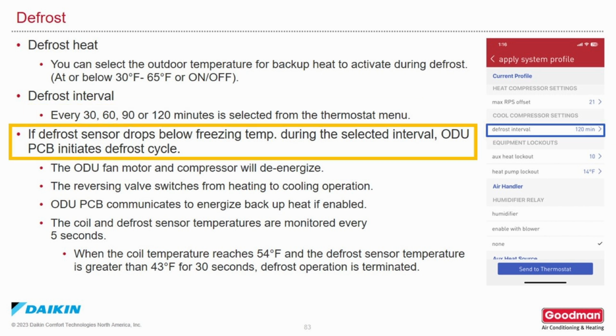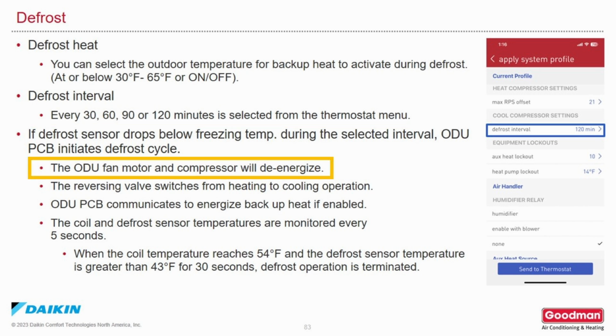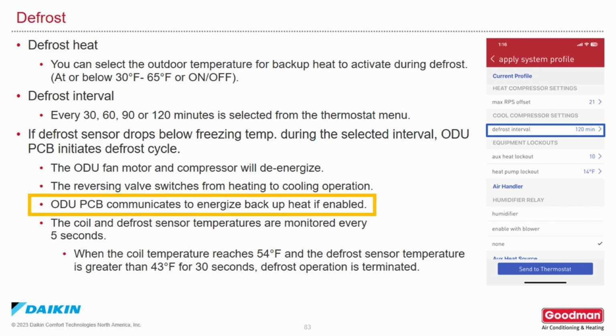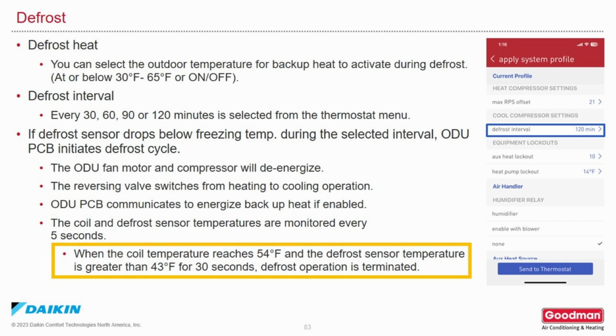If the defrost sensor drops below freezing temp during the selected interval, the outdoor unit circuit board initiates the defrost cycle. The outdoor fan motor and compressor will de-energize. The reversing valve switches from heating to cooling. The outdoor unit circuit board communicates to energize backup heat if that's enabled. The coil and defrost sensor temperatures are monitored every 5 seconds. When the coil temperature reaches 54 degrees and the defrost sensor temperature is greater than 43 for 30 seconds, defrost operation will end.